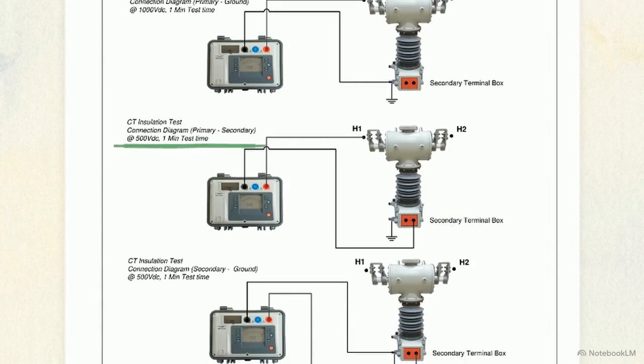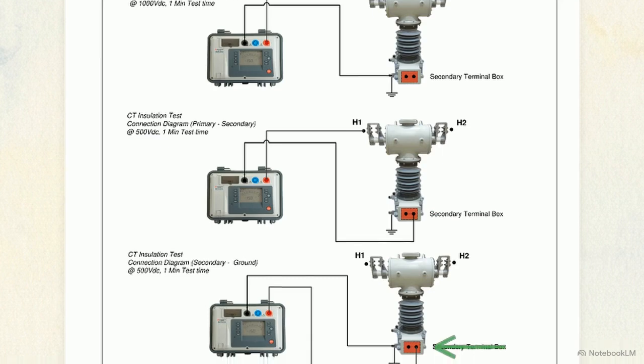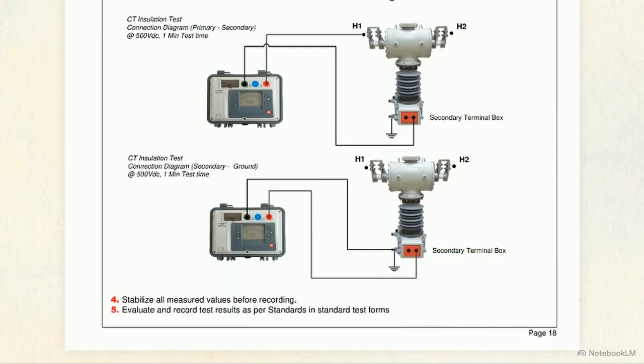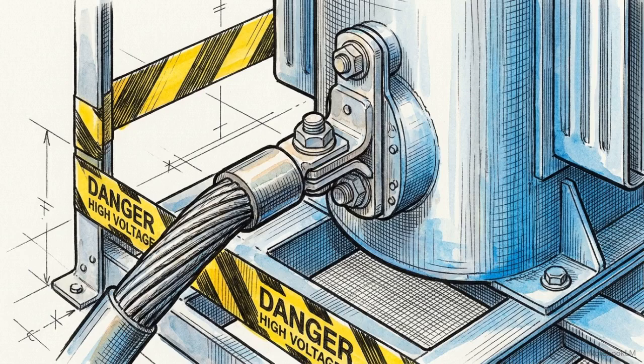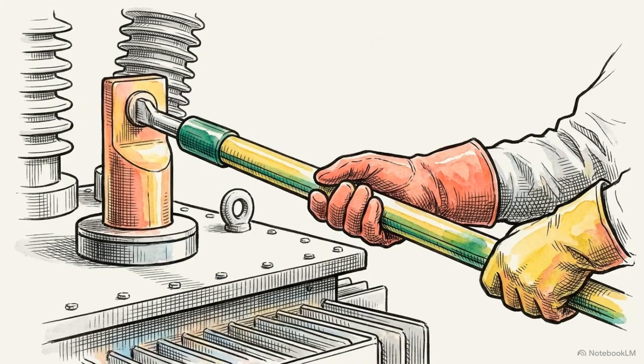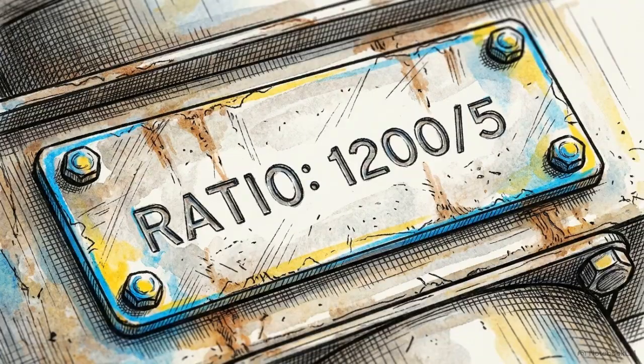The voltage is reduced to 500 volts DC, verifying isolation between the high voltage input and the sensitive relay outputs. Finally, the secondary to ground boundary is tested, again at 500 volts DC, confirming the secondary wiring is fully isolated from the chassis earth. These tests charge the transformer's internal capacitance. The technician must hold the measurement until the resistance readings stabilize, and then actively discharge the system after every test to neutralize stored energy. Once the insulation is proven sound, we move to the turns ratio test.